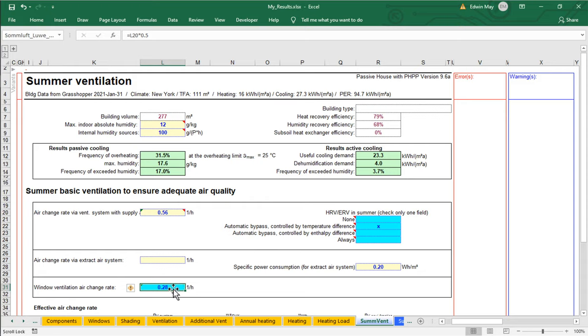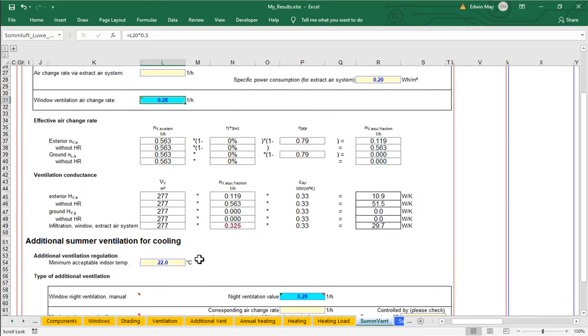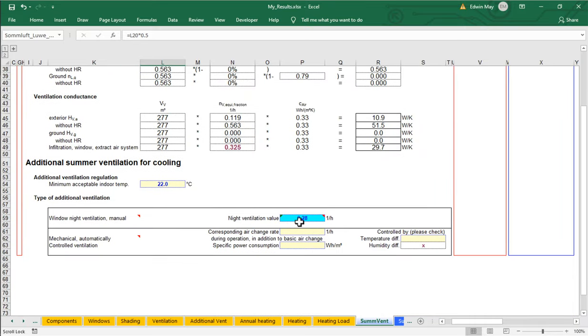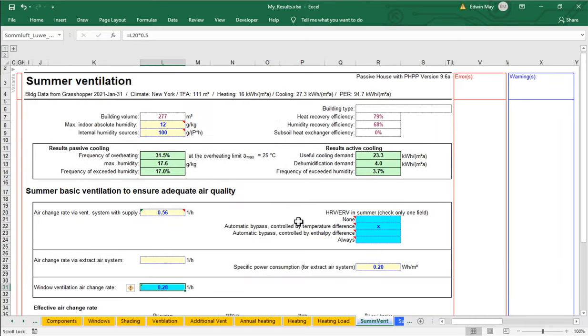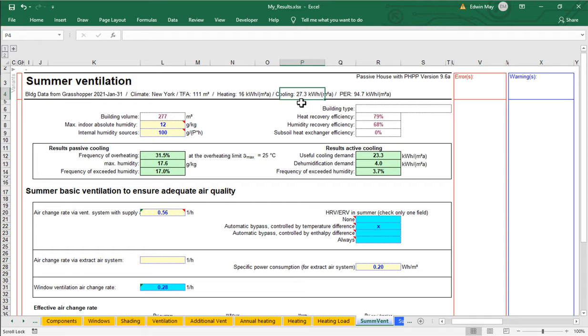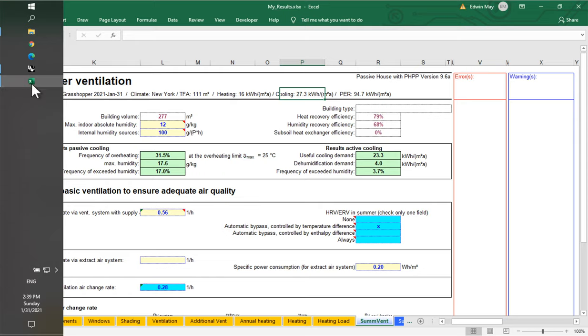And at 0.28 ACH in the daytime and at 0.28 ACH at night, how does that affect our cooling? Notice up here, our cooling has dropped to 27 kilowatt hours per square meter per year. We used to be at 30 something. So we've dropped down to 27. We could probably do even better than that.